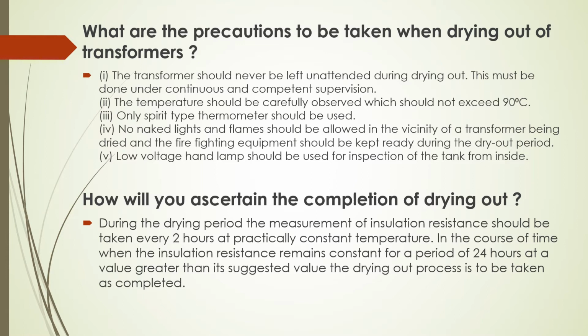How will you ascertain the completion of drying out? During the drying out period, the measurement of insulation resistance should be taken every 2 hours at practically constant temperature. In the course of time, when the insulation resistance remains constant for a period of 24 hours at a value greater than its suggested value, the drying out process is to be taken as completed.